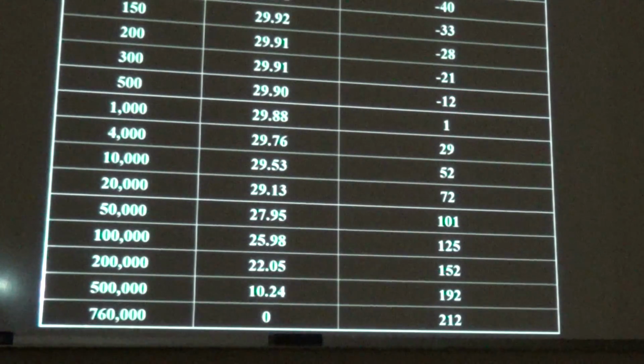So that's why when we put our vacuum gauge on, vacuum pump on, we bring the vacuum down to 500 microns, or on our gauge set it would look like 30 inches of mercury. We're boiling water inside that tubing at -12 degrees Fahrenheit. So we started boiling water much sooner. When did we start boiling water?